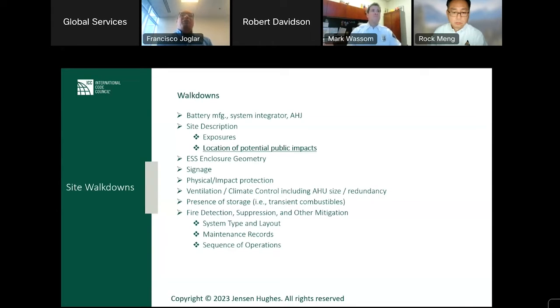Talk to operations about the sequence, right? There can be battery energy storage systems that have alarms due to the BMS, fire detection, and gas detection. All of them get reported to maybe even different groups of people within the company. If the battery management system is alarming, it may be an electrical problem that has nothing to do with fire, and you send a troubleshooting person to inspect, versus if you're detecting smoke, right?